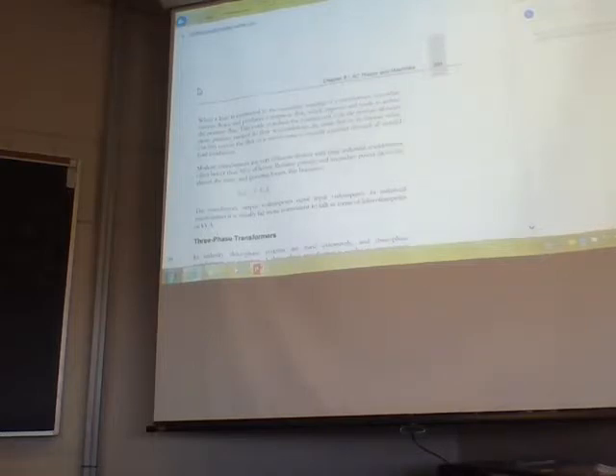When a load is connected to the secondary winding of a transformer, secondary current flows and produces magnetic flux, which opposes and tends to reduce the primary flux. This tends to reduce the counter EMF in the primary, allowing more current flow, reestablishing the main flux to its former value. For this reason, the flux of a transformer is virtually constant through all normal load conditions.